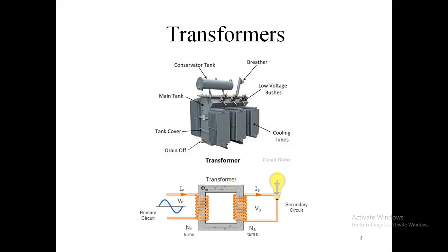Looking at the basic structure of the transformer, we can see the conservator tank, the breather, and the low-voltage bushings from where we take the low-voltage supply. The main tank contains the transformer windings along with the transformer oil and accessories. There are cooling fins used to cool the transformer oil when it gets heated, and a drain-off used when maintenance work needs to be done to remove the oil.